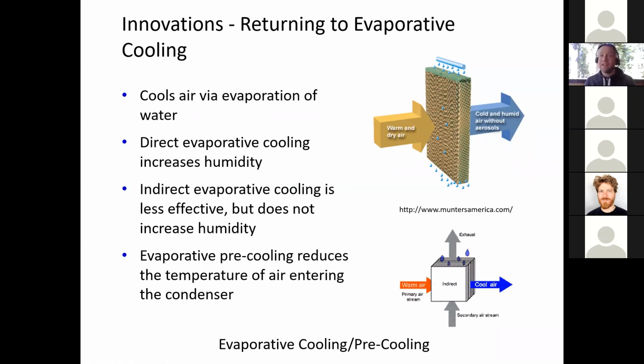They do use water, obviously, and in a drought condition that might be a concern. But if you're using evaporative cooling instead of traditional air conditioning, a recent study at UC Davis's Western Cooling Efficiency Center compared the water usage of electricity versus evaporative cooling, and found evaporative cooling uses less water than electricity-based air conditioning, because the power plant supplying that electricity also uses quite a bit of water across most of the Western United States.